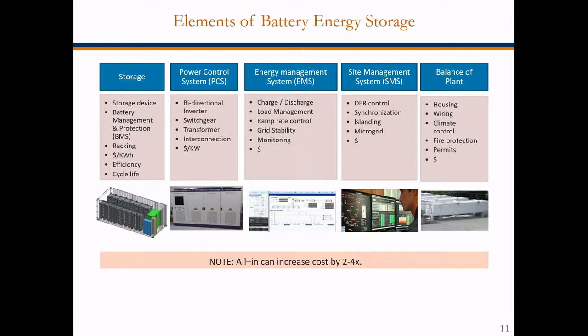When you get into the site management system, that's your microgrid controller. For instance, if you want PV, meaning solar power, to charge your battery and or the grid during certain operations—say if the grid's on—the site management system allows that to happen. If the grid goes out and you want excess PV to feed your load, and any excess to charge the battery, the site management system is what allows that to happen. Last but not least is your balance of plant.